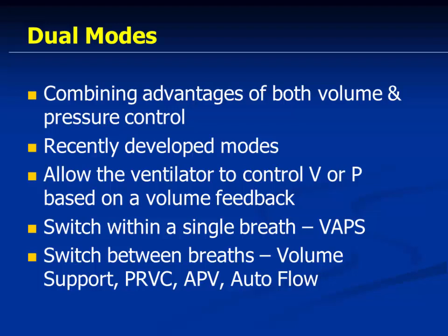So in dual mode, what is happening? We are trying to guarantee a tidal volume as well, whereas we are keeping flow variable. So we are enjoying both sides of the fence. So they combine the advantages of both volume control and pressure control.